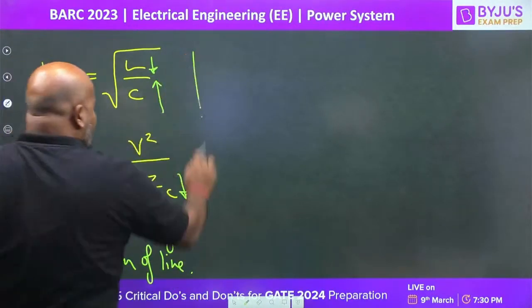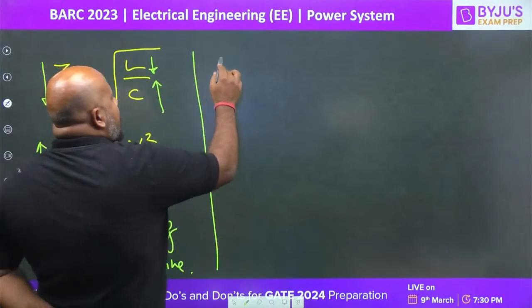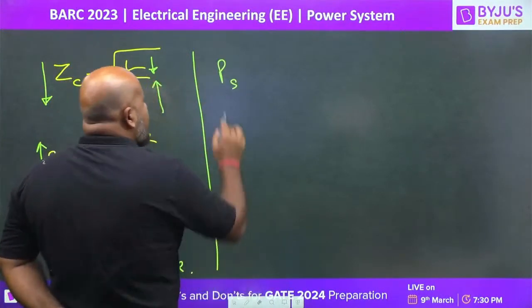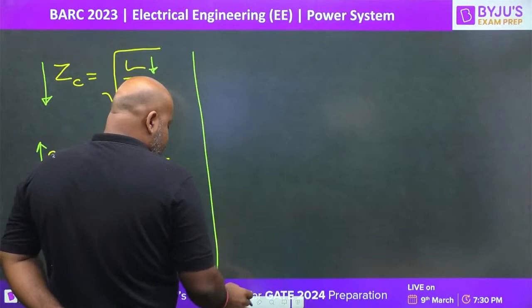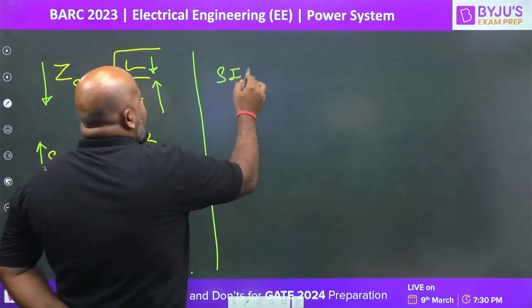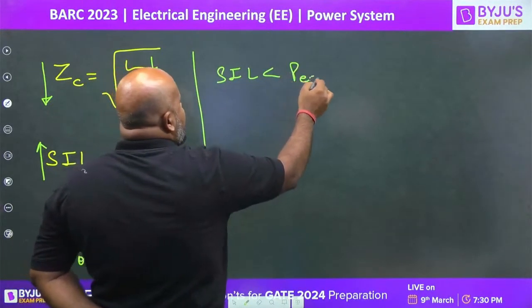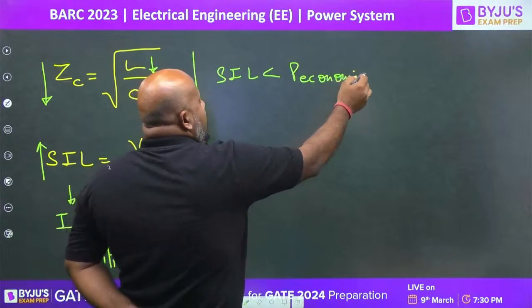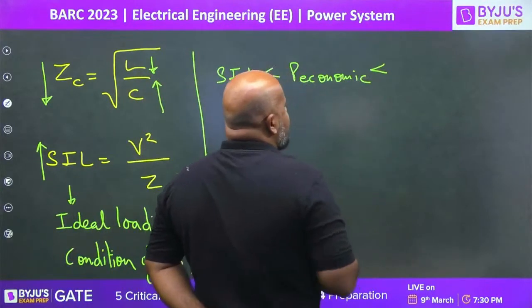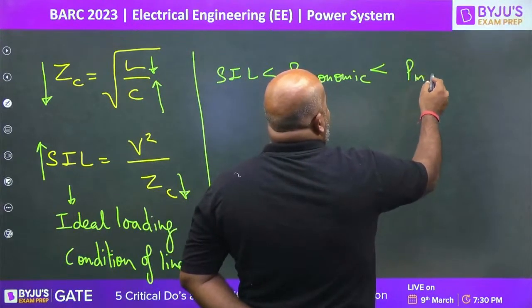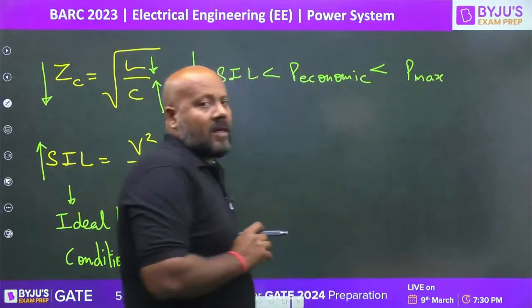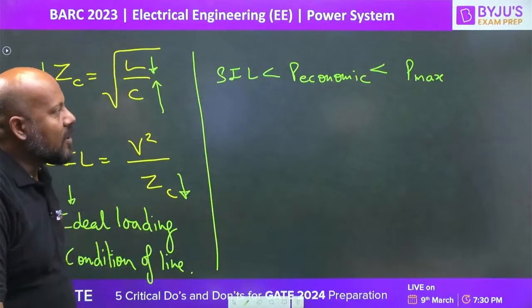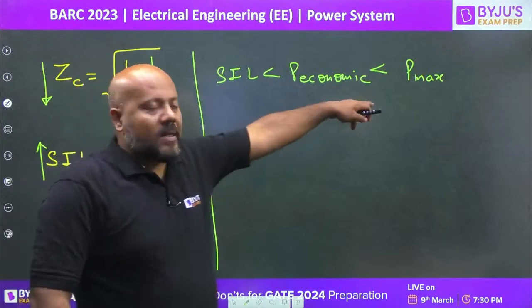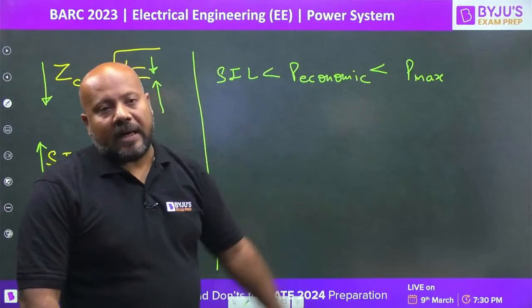If you talk about the economic loading of the line, economic loading of the line is always greater than surge impedance loading, and it is less than the maximum power which can be transferred over the transmission line, because if you reach this level, then stability is going to be highly compromised.